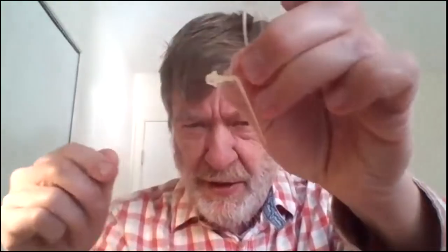Remember, hearing aids have two transducers, a mic and a speaker. The mic changes sound into electricity, the hearing aid amplifies the electricity, and then the speaker changes it into sound again. So a speaker is just a backward mic. A mic is a backward speaker. A frown is an upside down smile. A smile is an upside down frown. Okay? So, in hearing aids, the speaker is called a receiver. It's because it receives the current. You and I would call it a speaker. Anyway, thin tube, and then sending it out into the dome.